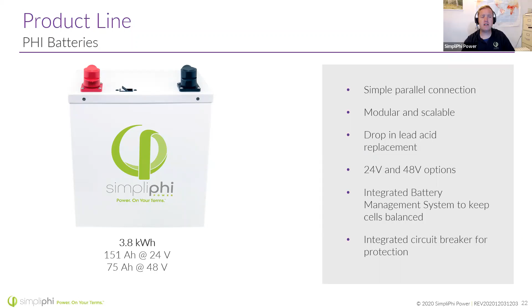I want to take a moment here to make sure you never run our batteries in series - you always want to do parallel. So if you have a 48 volt system, buy 48 volt batteries. Don't go out and buy two 24 volt batteries and run them in series. It has a simple integrated battery management system, mainly there to keep the cells balanced, and an integrated circuit breaker.